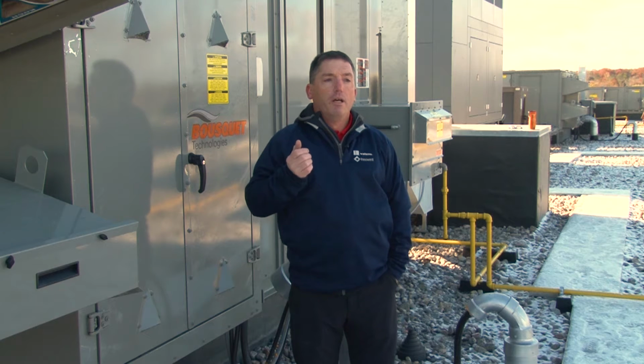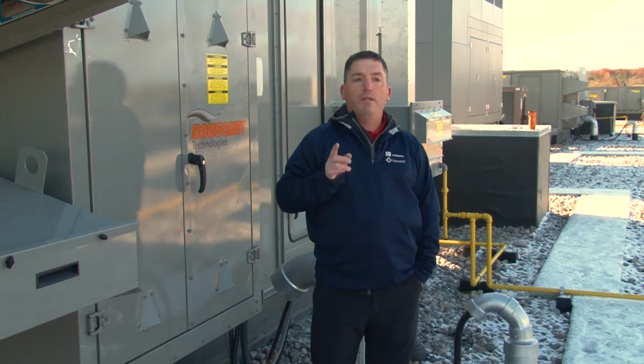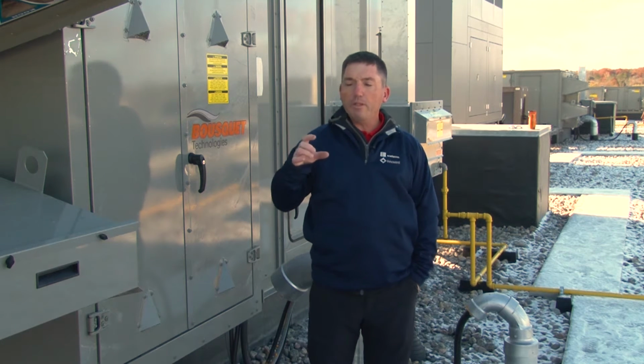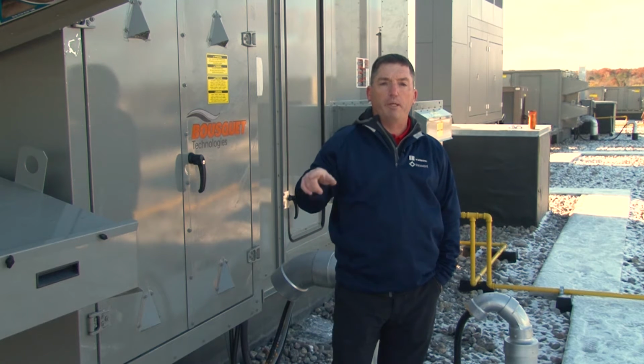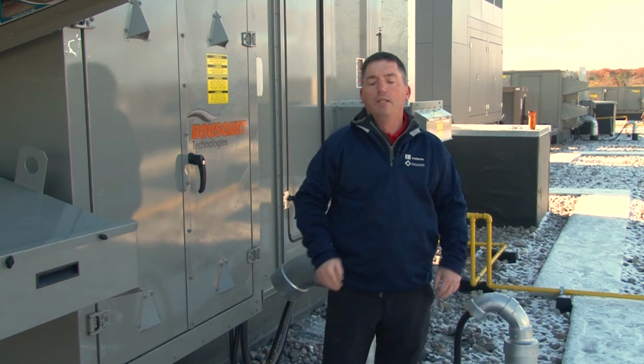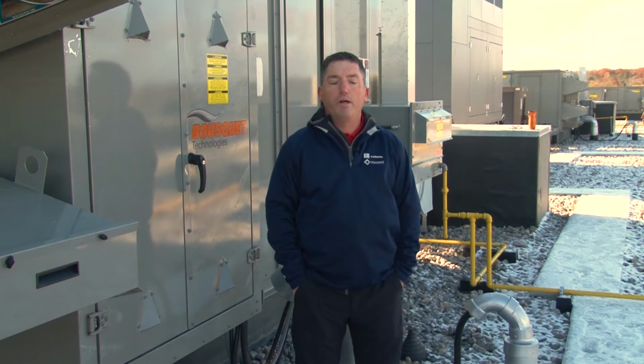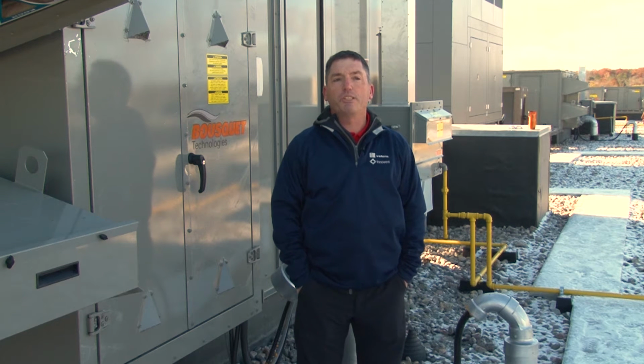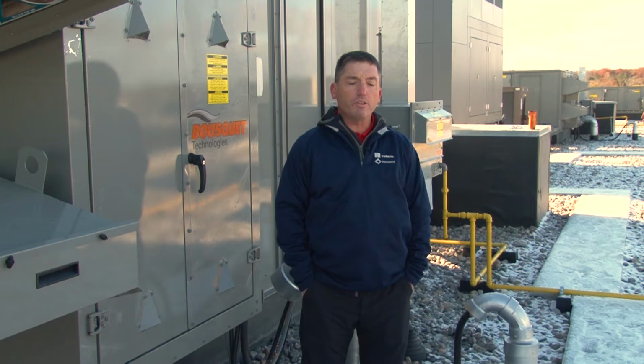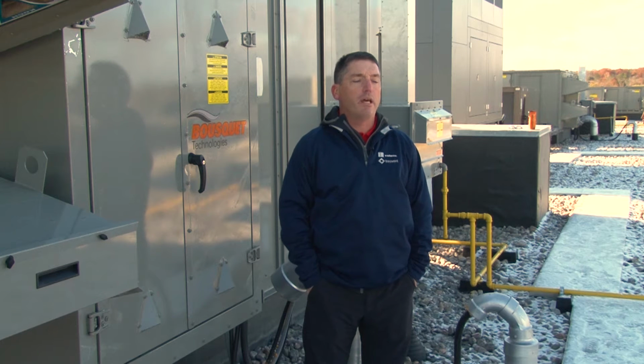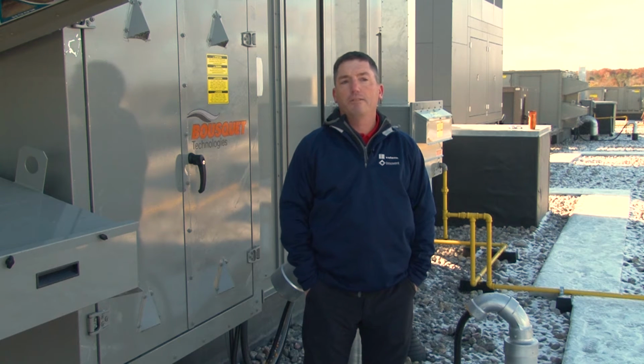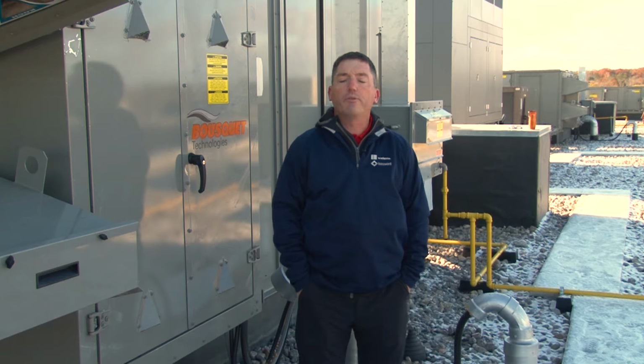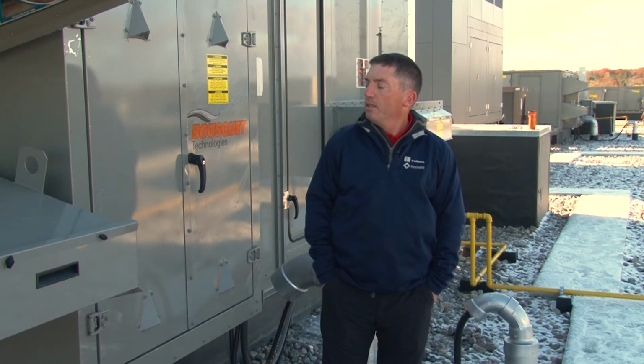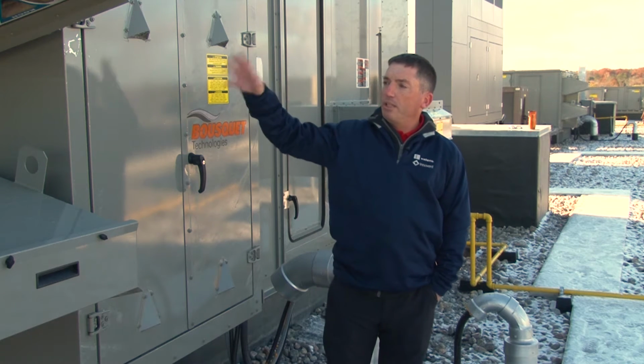The only other maintenance item on that wheel, because it rotates, is a small motor and a drive belt that wraps around the outside of the wheel. Again, it's a very low RPM, roughly 60 RPM or less, so there's not a lot of stress on it. That drive belt should last somewhere between 3 to 5 years before you need to take a look at replacing it. So that is the exhaust side.